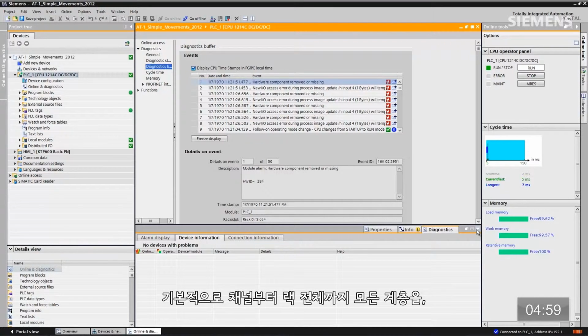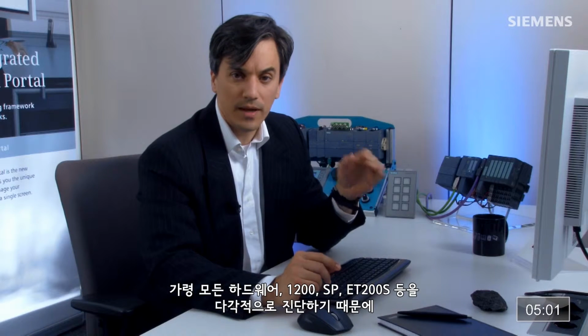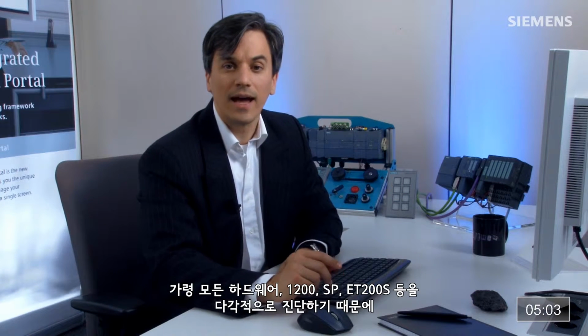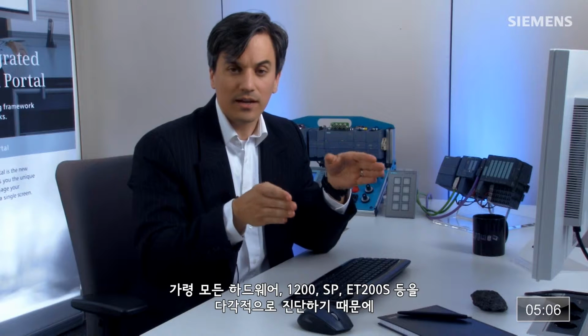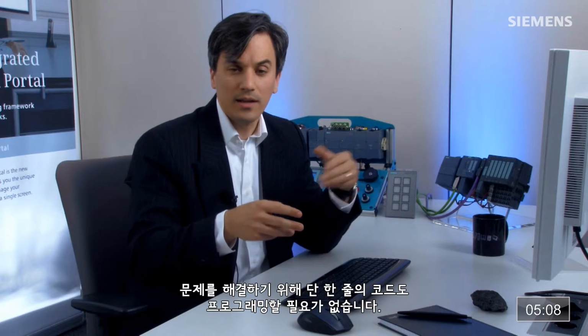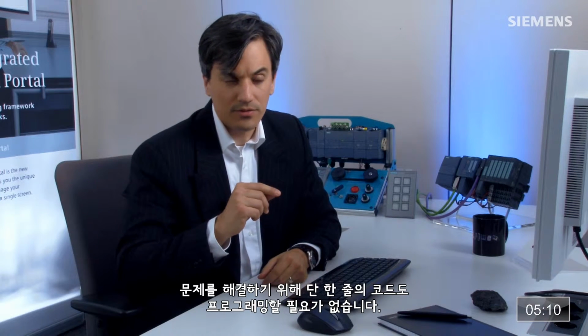Problem is now solved. It goes back and scans everything, and we have an outgoing message, and everything is now green LEDs. So basically, we have the ability for all of our hardware, 1200, SP, ET200S, to have every single layer of potential diagnostics, from the channel all the way to the entire rack, and you don't have to program one line of code to get any of this.